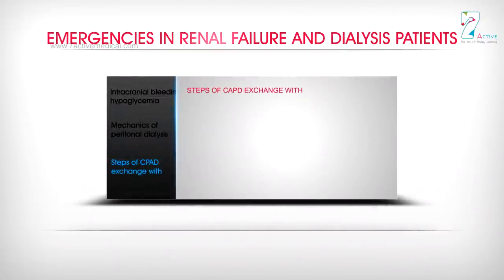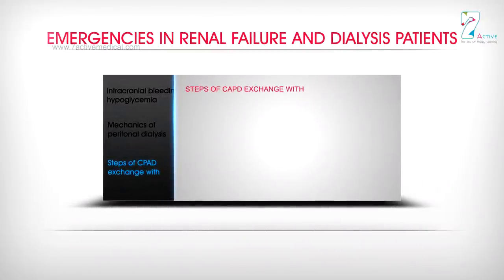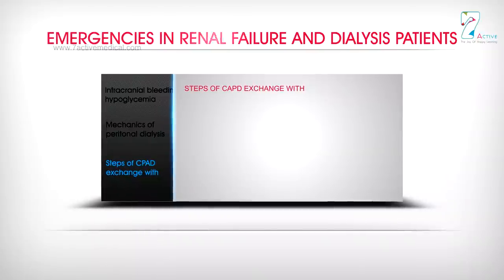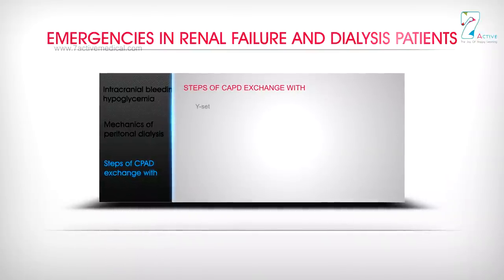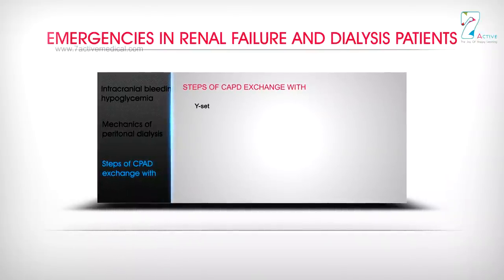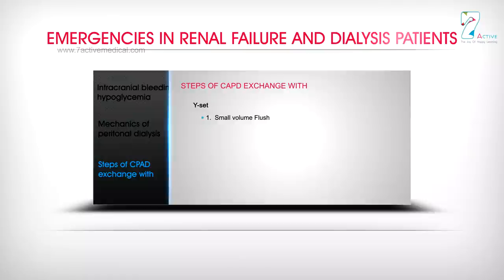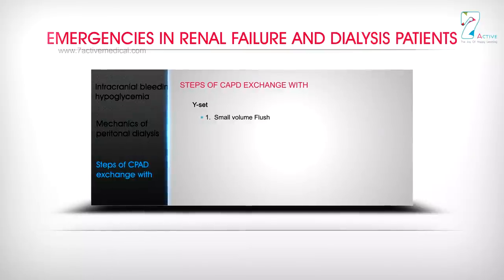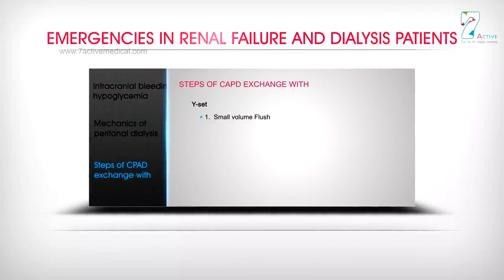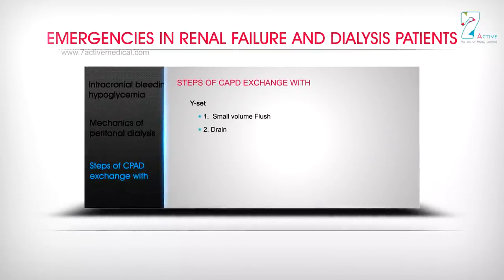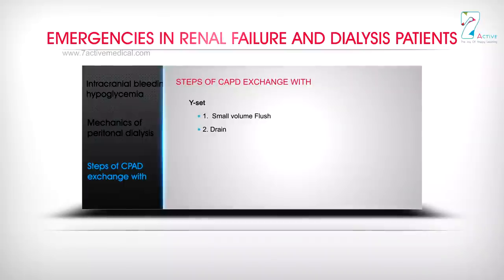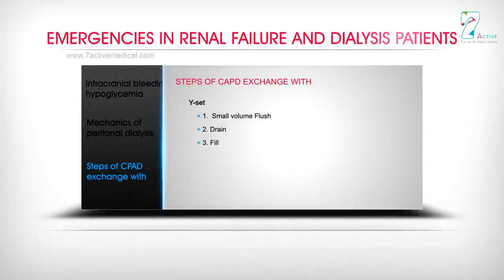Steps of CAPD exchange with Y-set: 1) small volume flush; 2) drain; 3) fill; 4) disconnect.